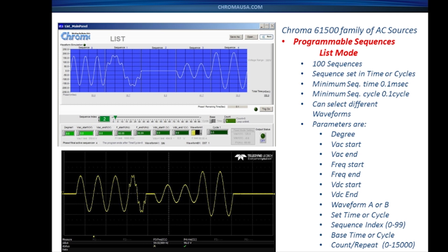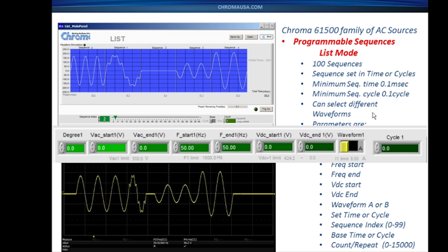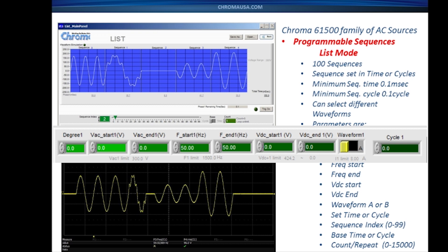The parameters are loaded in the software where you can set the phase shift or phase angle starting point in degrees, a start and end voltage, start and end frequency. You can also program a start and end DC offset, and of course, you can select between two different waveforms. Here I've got it selected for cycles, so you can put in anything from multiple cycles all the way down to 0.1 cycle or one-tenth of a cycle.